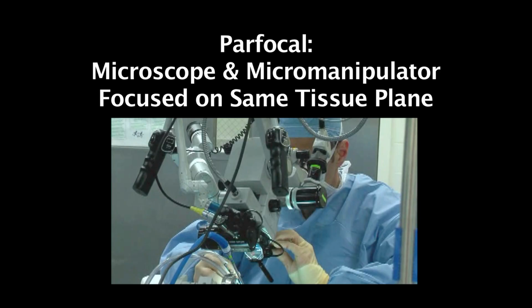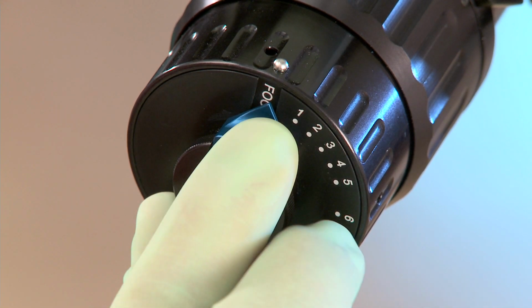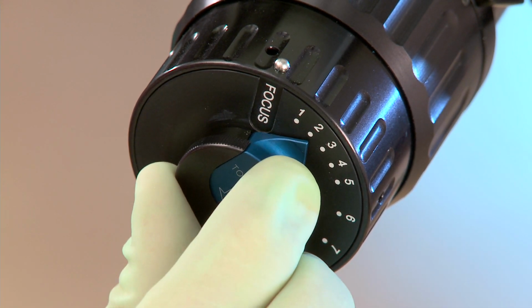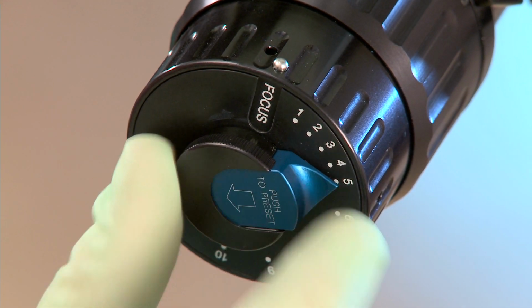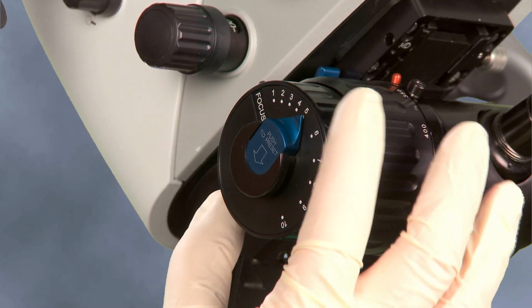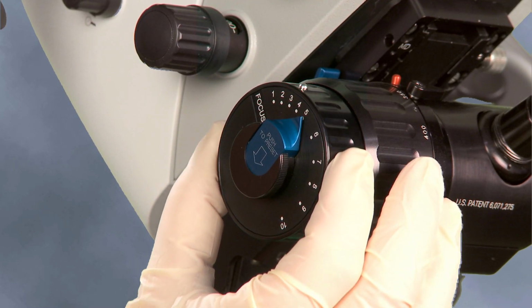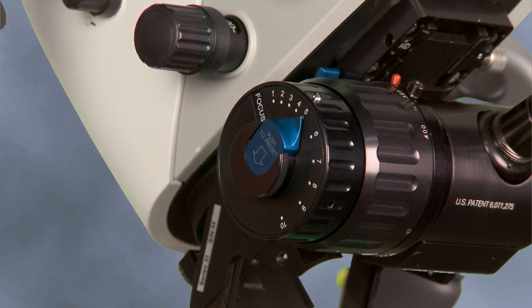The spot size selection knob works properly when the microscope and micromanipulator are parfocal, meaning they are both focused on the same tissue plane. The blue defocus limiter tab can be set to restrict how far the spot size knob can be turned. This feature enables the surgeon to defocus the beam to a predetermined setting without looking away from the microscope. This is often used to apply energy for hemostasis.